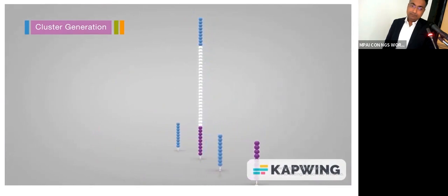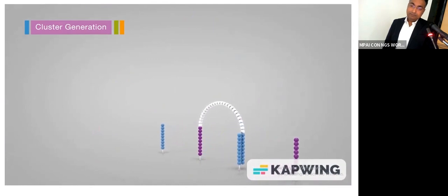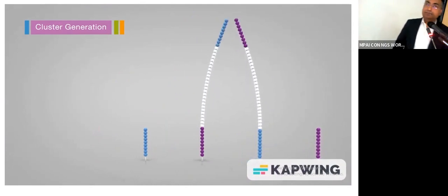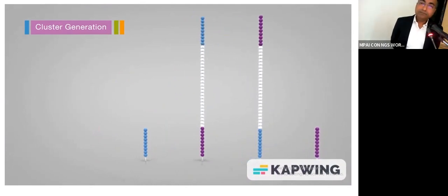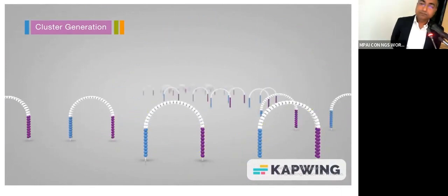In this process, the strand folds over, and the adapter region hybridizes to the second type of oligo on the flow cell. Polymerases generate the complementary strand, forming a double-stranded bridge. This bridge is denatured, resulting in 2 single-stranded copies of the molecule that are tethered to the flow cell. The process is then repeated over and over and occurs simultaneously for millions of clusters, resulting in clonal amplification of all the fragments. After bridge amplification, the reverse strands are cleaved and washed off, leaving only the forward strands. The 3' ends are blocked to prevent unwanted priming.